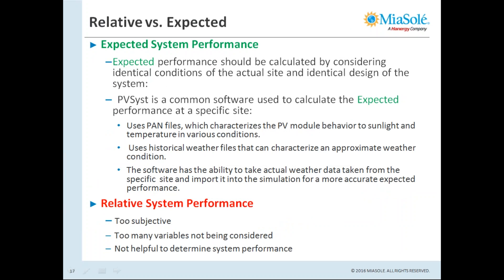To do a proper actual-versus-expected comparison, one approach is to use software like PVSyst, which can take PAN files that characterize PV modules in terms of behavior under light and temperature. This software utilizes weather files using weather data averaged over 10, 20, or even 30 years at a particular location to simulate accurate expected performance of a modeled system. You can even import actual weather data collected in the field for a closer comparison, ensuring you're using truly comparable performance data.